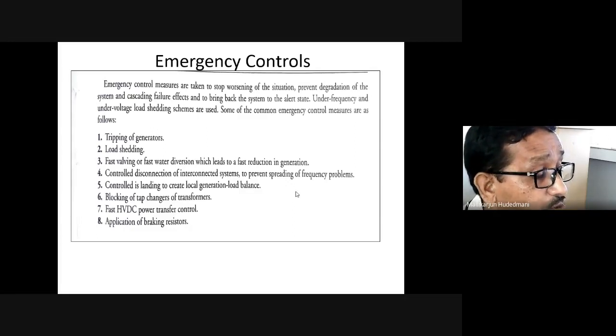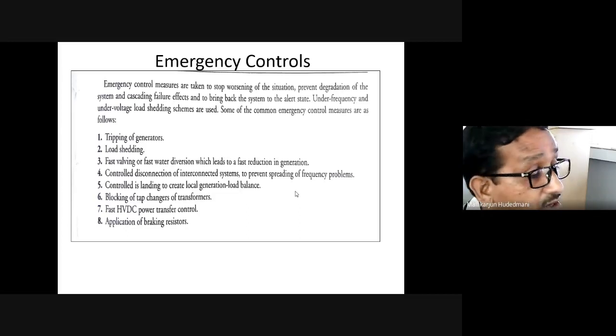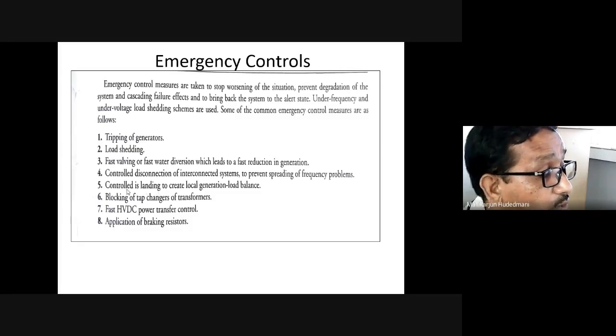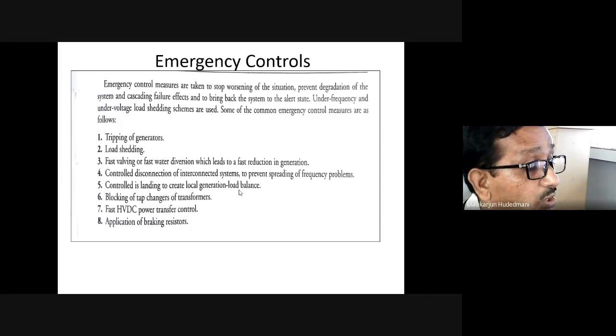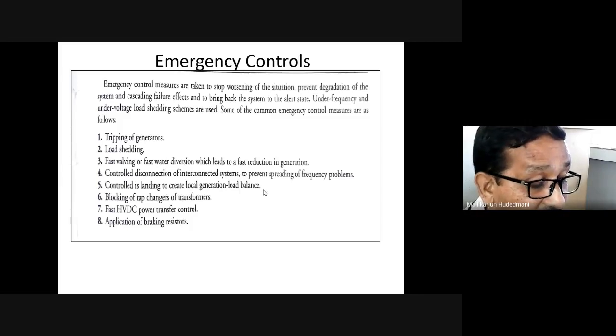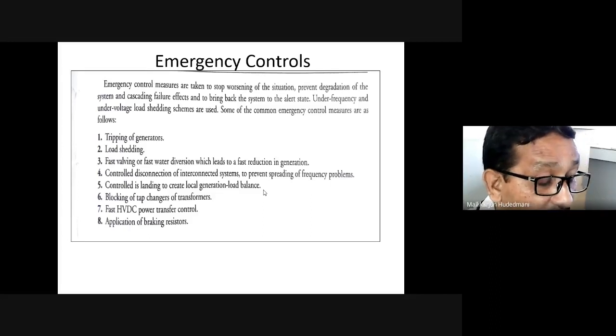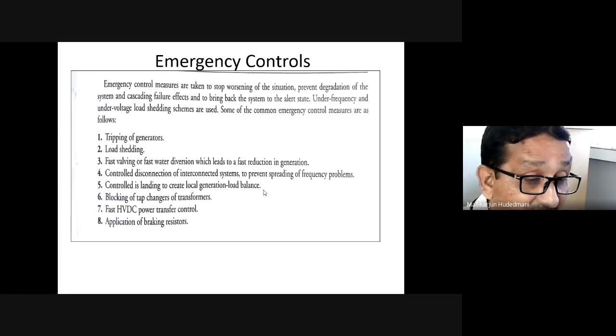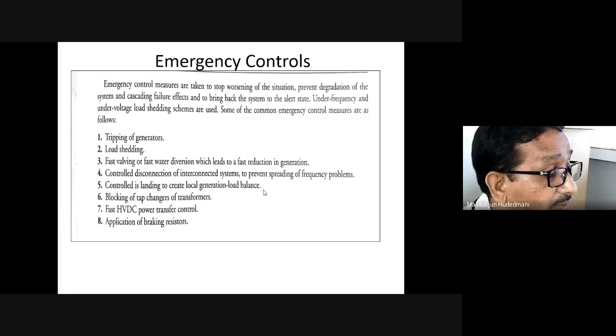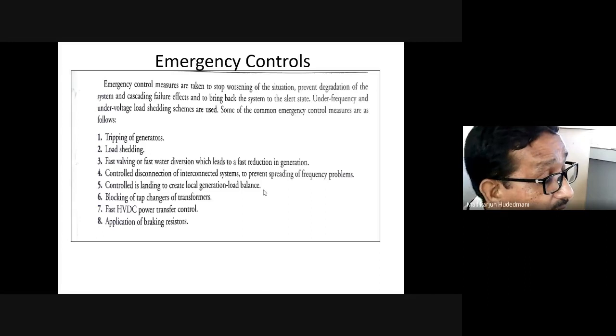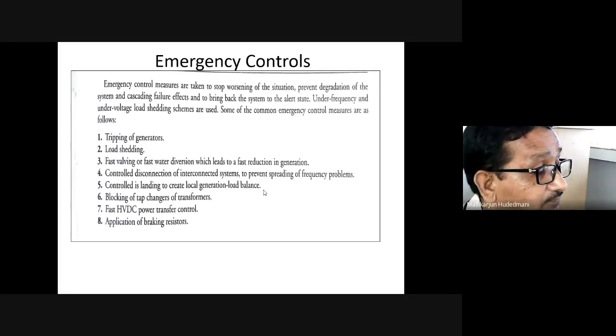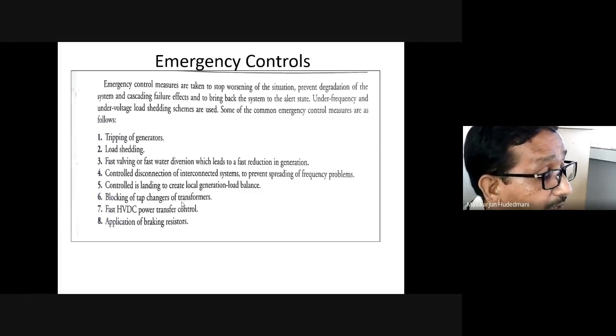Then control the disconnection and the interconnection of the system. Prevent spreading of frequency problems. I have to disconnect the load in steps, gradually, in a proper fashion, so that the frequency deviation will not spread to a large area and will come under control. And controlled islanding: controlling the islanding to create a local generation and load balance. It means segregating the areas, an area of generators only, an area of load only, a substation. It's called islanding. So islands must be isolated and each island has to be operated independently to the possible extent, so that with the disconnection from one to another, prevention at that point can be addressed carefully.